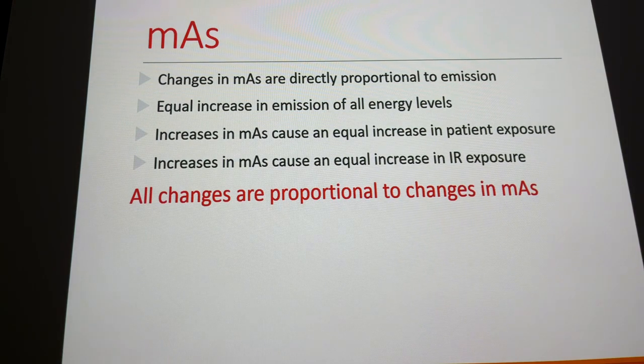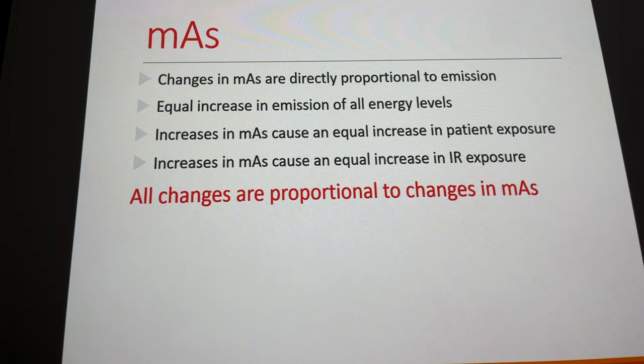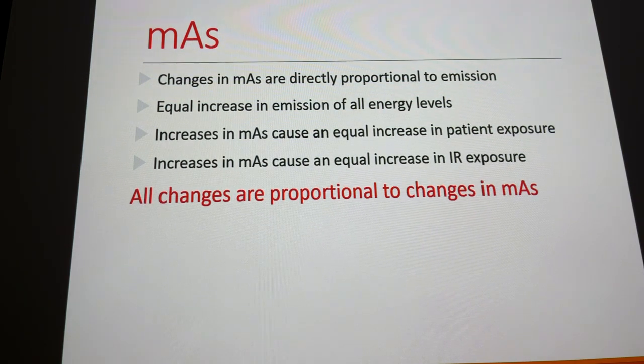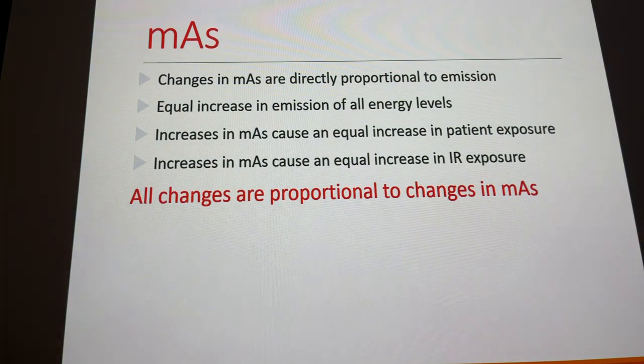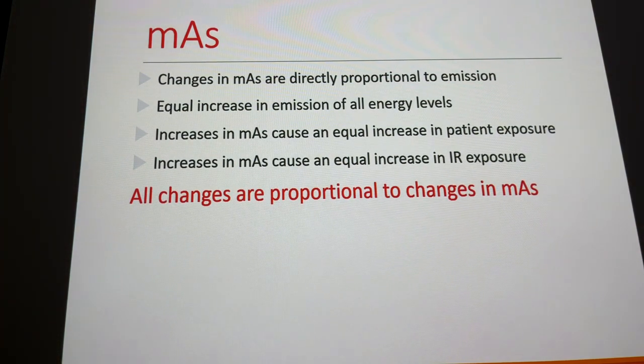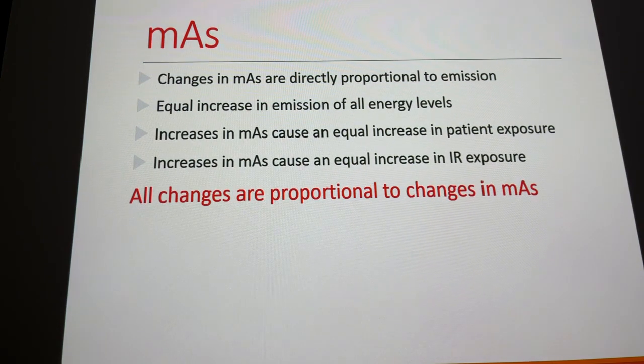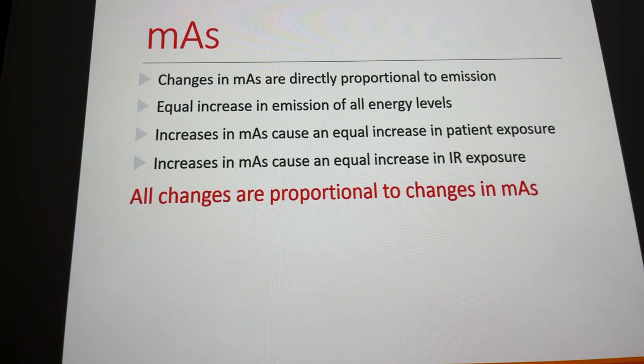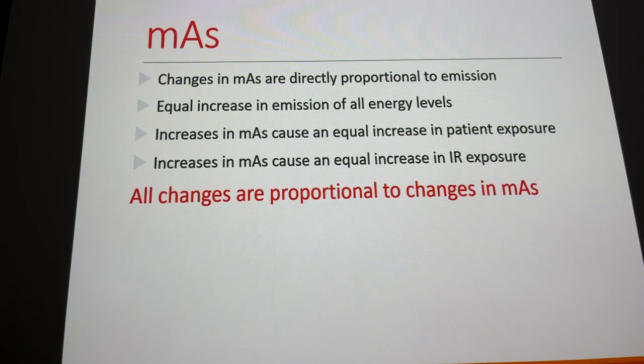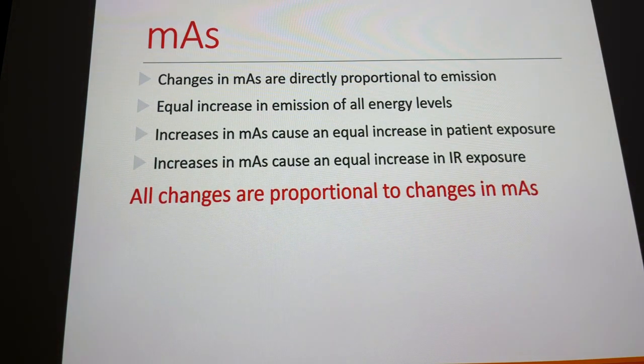Changes in mAs are directly proportional to X-ray emission — equal increase in emission all the way across the board. You don't change the percentage distribution at all. Thinking about the bremsstrahlung spectrum, the only thing that happens is the numbers increase: equal increase in patient exposure and equal increase in image receptor exposure, all proportionally.